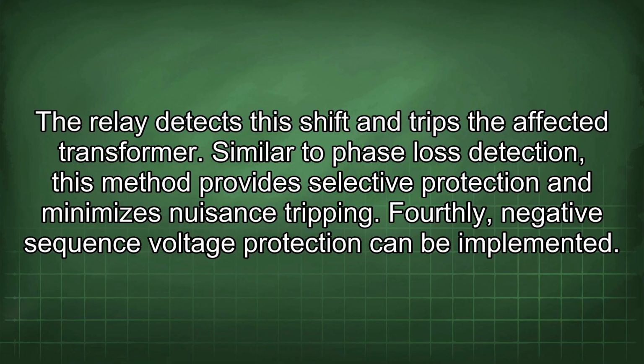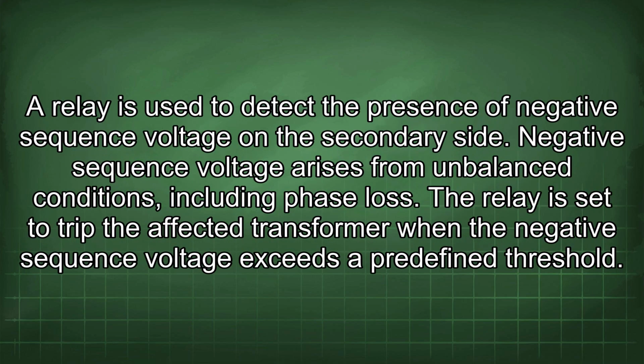Fourthly, negative sequence voltage protection can be implemented. A relay is used to detect the presence of negative sequence voltage on the secondary side. Negative sequence voltage arises from unbalanced conditions, including phase loss. The relay is set to trip the affected transformer when the negative sequence voltage exceeds a predefined threshold.